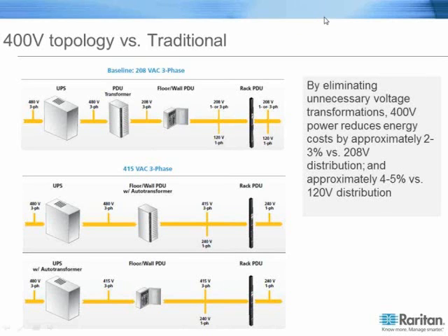So today we're seeing 480 coming in from utility into a UPS that has an auto transformer. Most of the major UPS manufacturers are doing this now, or we're going into a floor or rack PDU, an RPP, or a remote power panel, that has that auto transformer built in, and now we can deliver straight 415 right to the rack level PDU. Anything we can do to help reduce heat on the data center floor, and if we can reduce energy costs, if we can reduce that distribution cost, not having that 2, 3, 4, 5% loss from stepping it down, that's a plus. Any efficiencies we can deliver to the data center, we're delivering such high loads right now, even single-digit percentages can make a difference in the amount of product we can deploy.